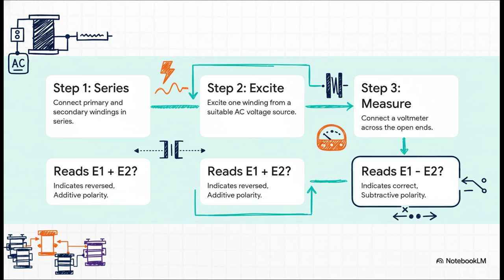Why is subtractive polarity the one we want? It comes down to safety. The industry prefers it because it avoids a huge voltage difference between two adjacent terminals. Keeping that electrical stress low massively reduces the risk of insulation failure or arcing, making the whole setup safer and more reliable long term.